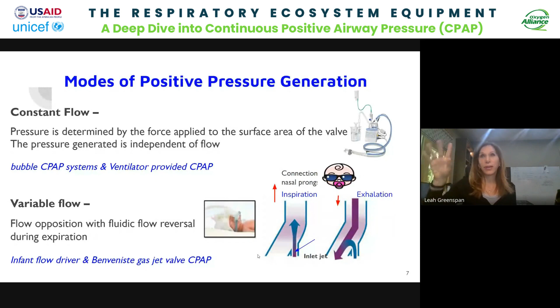And there's another effect which flips. As you can see in exhalation, the gas is going down. So the flow flips, the flow of the inhaled flips into the expiratory limb during expiration to maintain stable CPAP throughout the cycle. Now, the important point to remember here is that the pressure that is generated is dependent on flow. When you increase the flow in these types of devices, you are increasing the pressure. So I just wanted you to keep all of that in mind, and let's forget about all of this now.